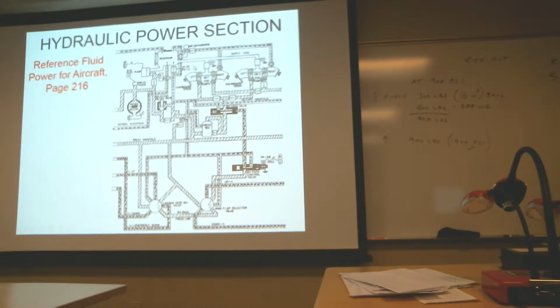They do have a standpipe in the reservoir, and we can kind of figure out where the main system is and what the auxiliary system is. The main system is plumbed so that we receive fluid from a standpipe and it goes directly into the circuit. And then if we've got an auxiliary pump, usually that's attached to the very bottom of the reservoir. So that's why they did that here. They just got a very small opening down at the bottom that draws fluid from the very bottom.